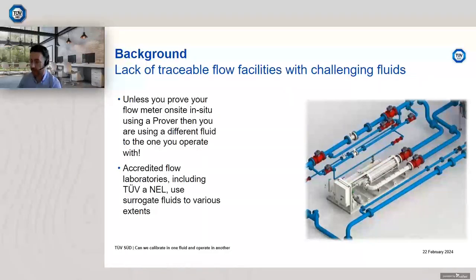In NEL/TÜV Süd are using surrogate fluids in a lot of cases. We use nitrogen for gas, but we also now have carbon dioxide, and we also have a rig that can offer methane/natural gas and also hydrogen, or methane in place of natural gas. For our oils, we don't use crude oil, we use mineral oils. So again, we're using surrogate fluid, but we try to match other key parameters such as Reynolds number or fluid viscosity, for example, and maybe not quite the density. I'll show you some of the data to back that up.